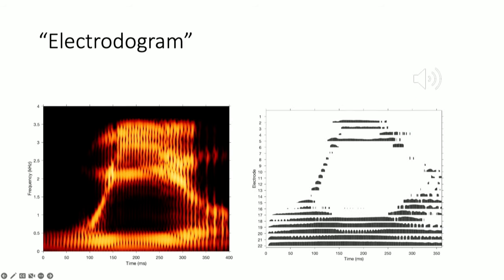Another helpful way to visualize the signal being sent to a cochlear implant is the electrodogram. A spectrogram plots the spectrum of frequencies of a given sound over time — in this case, of the speech signal 'wheel.' The electrodogram is similar to a spectrogram, and it plots the current levels of each of the 22 electrodes in a cochlear implant, where each electrode can be thought of as corresponding to a single frequency band in a vocoder.